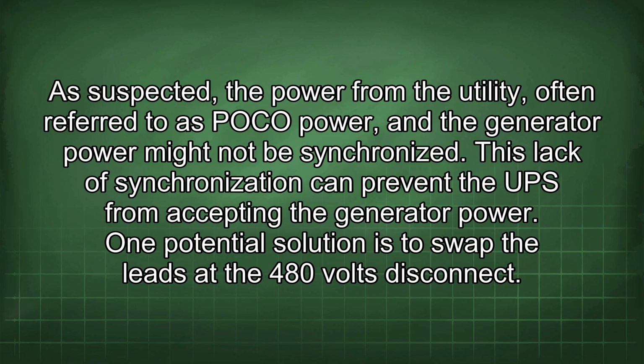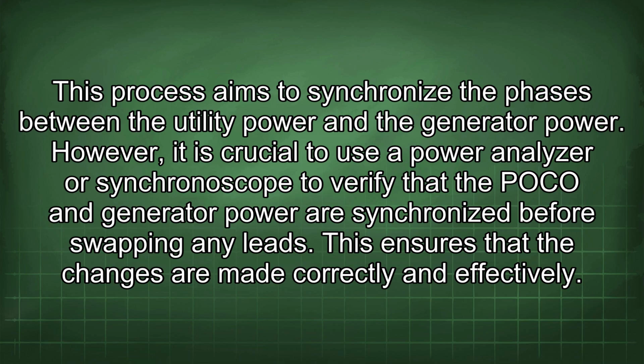One potential solution is to swap the leads at the 480 volts disconnect. This process aims to synchronize the phases between the utility power and the generator power. However, it is crucial to use a power analyzer or synchronoscope to verify that the POCO and generator power are synchronized before swapping any leads. This ensures that the changes are made correctly and effectively.